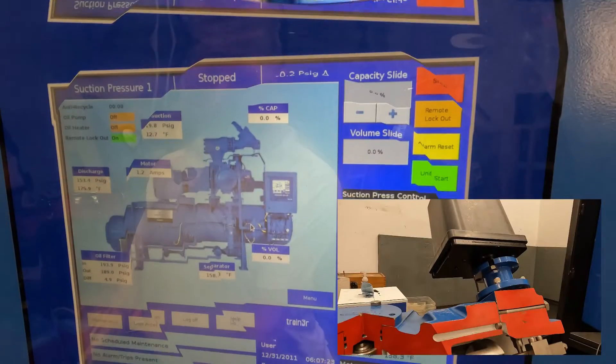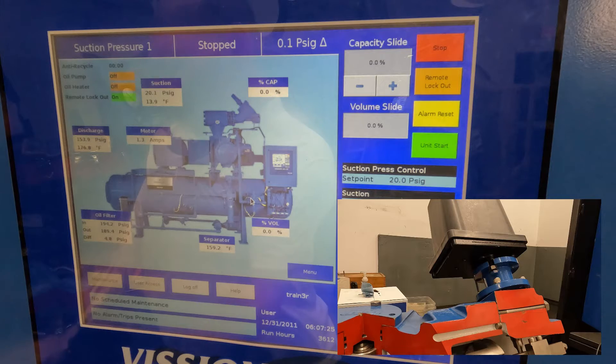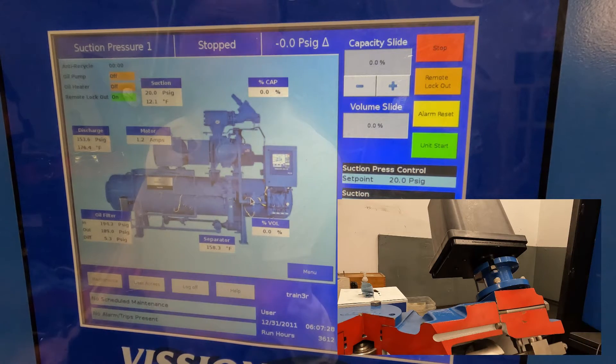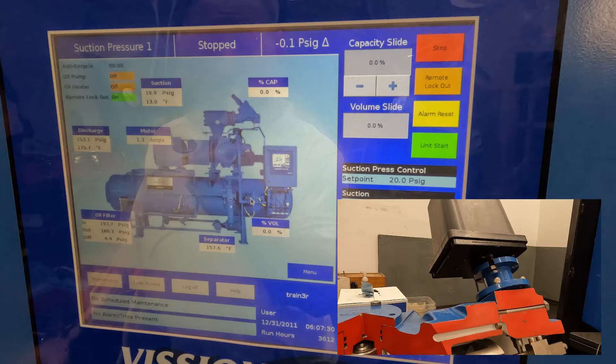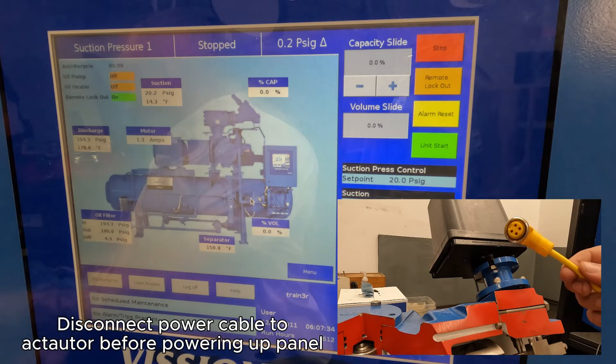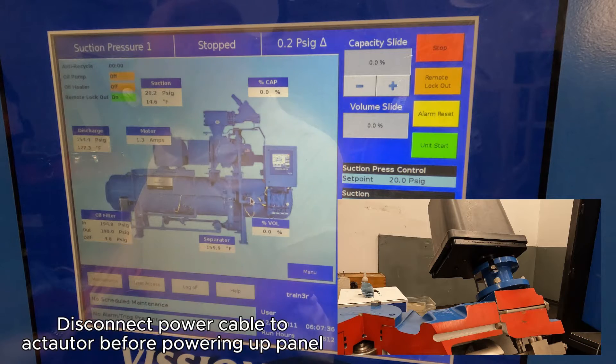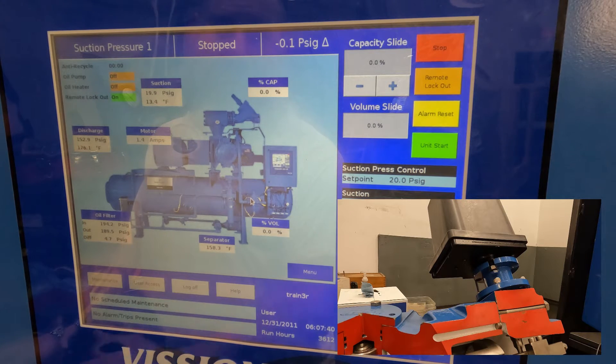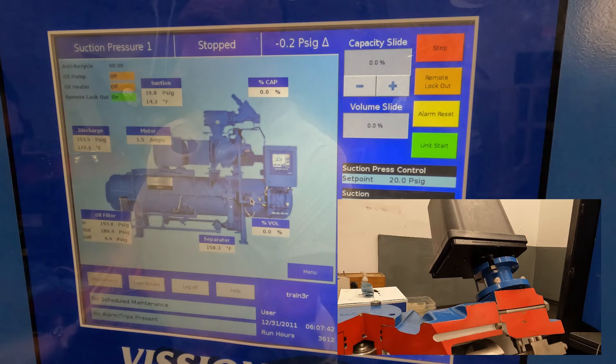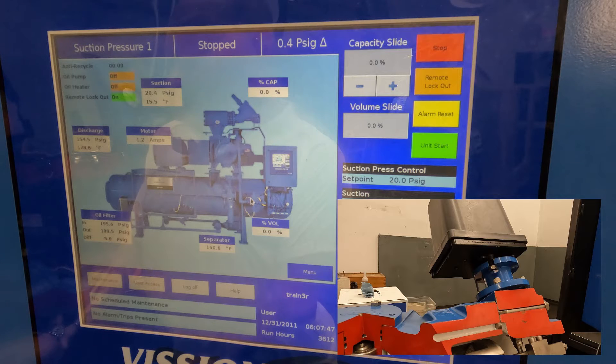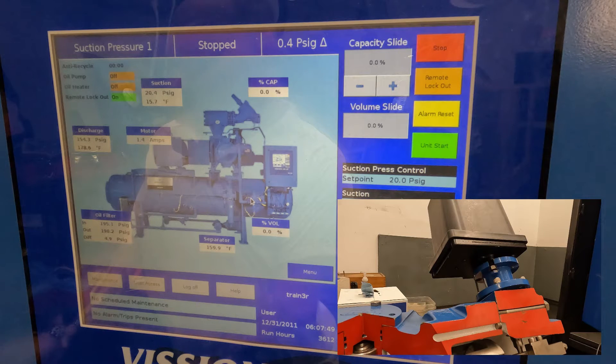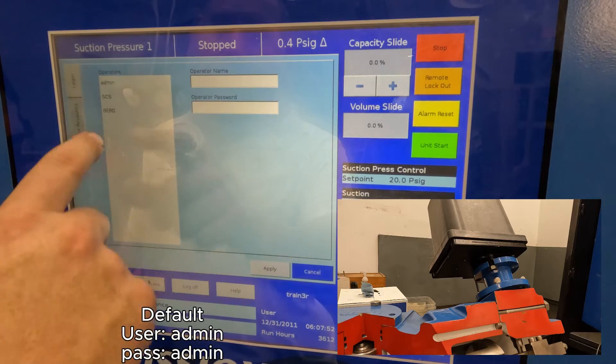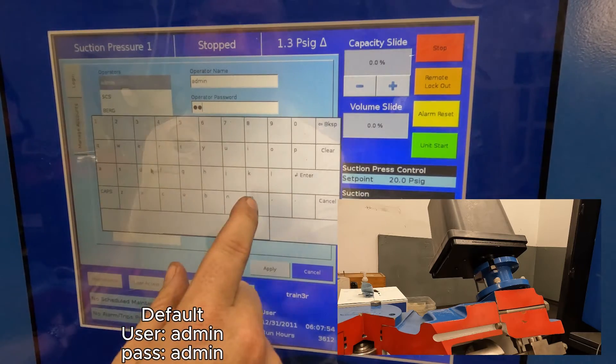So when powering up a new panel or if you've removed the actuator command shaft or done some sort of service work, the important part is to disconnect and remove the power cables to the actuators before you start up anything else. The reason being, when the panel starts up, it's going to automatically start talking to the actuators and try to put it in the position that it believes it should be in from where it thinks it is, not necessarily where it actually is. So from there, we're going to log in to the panel.